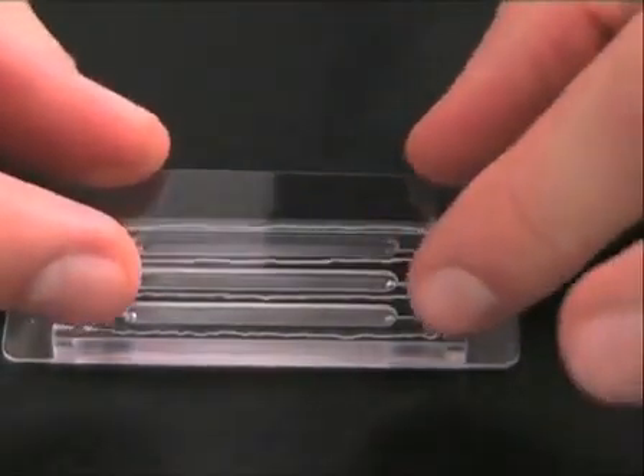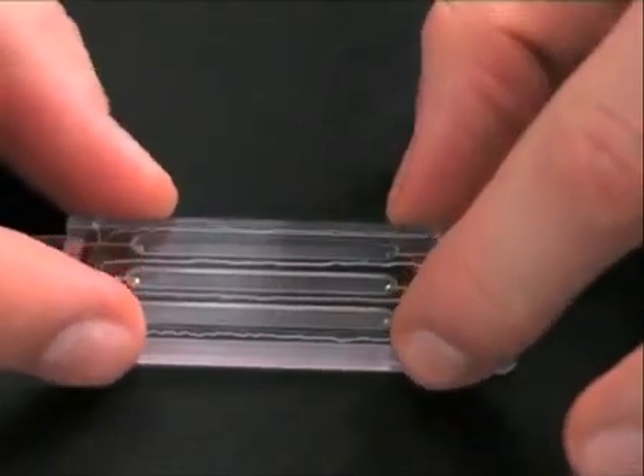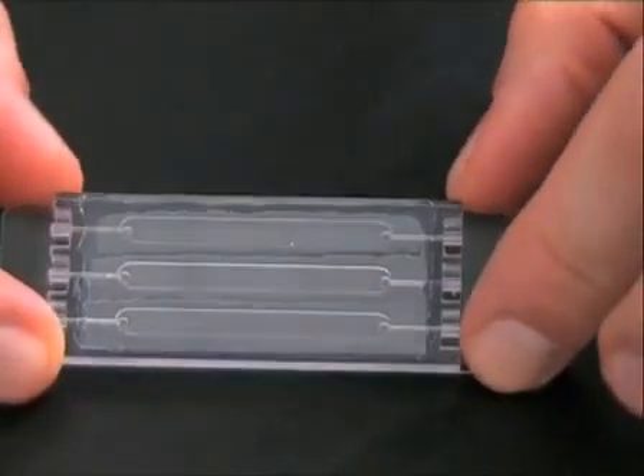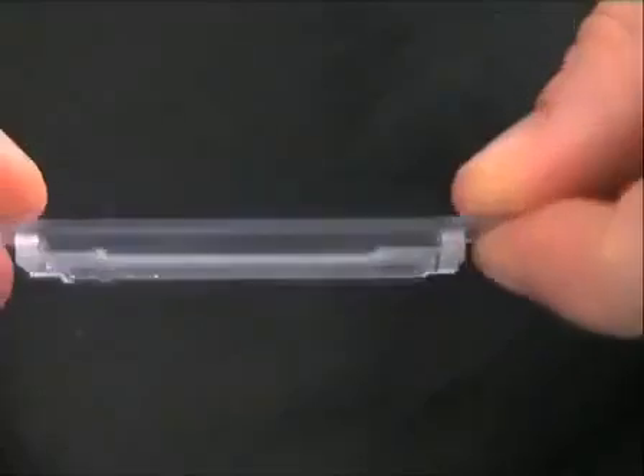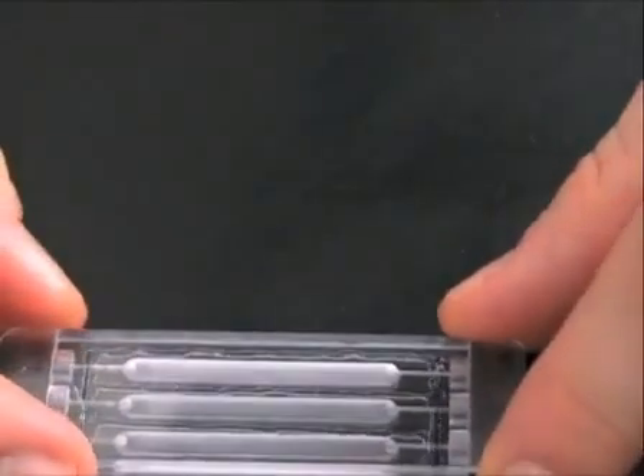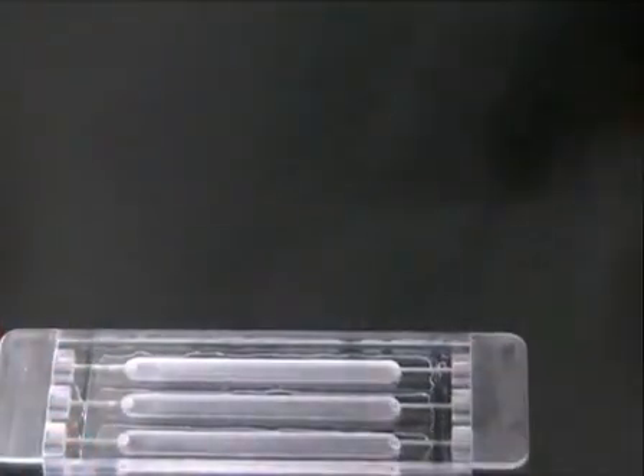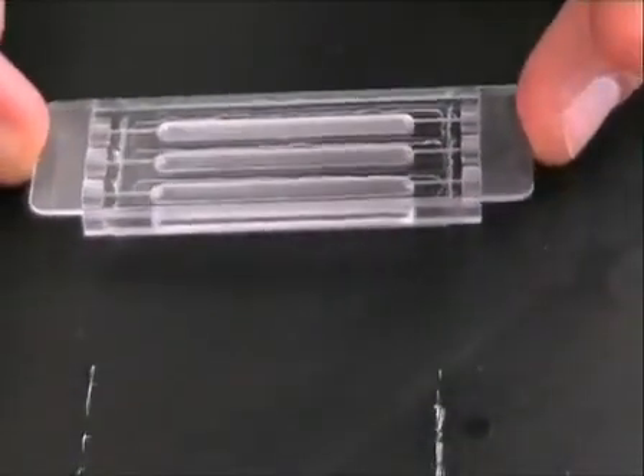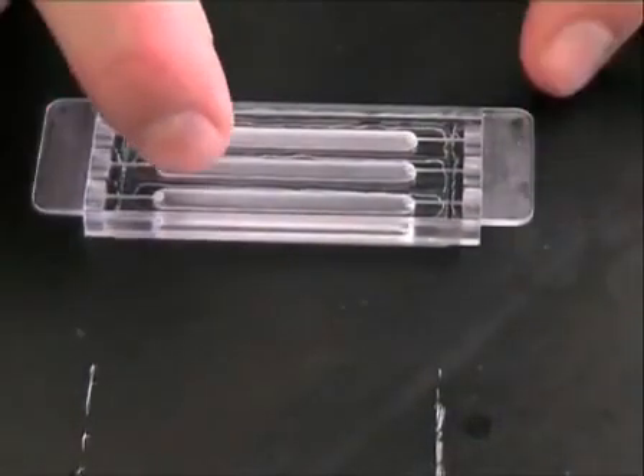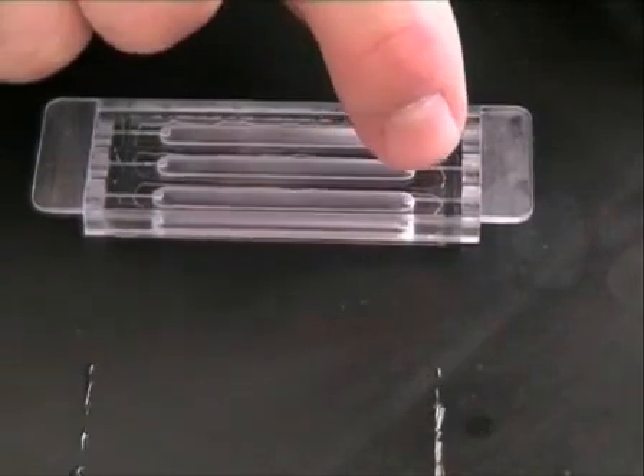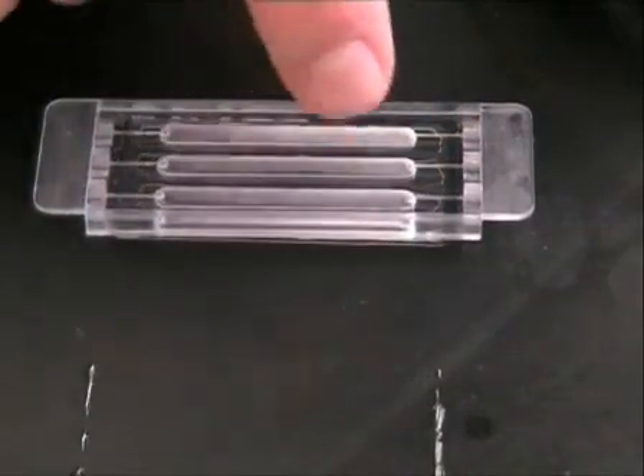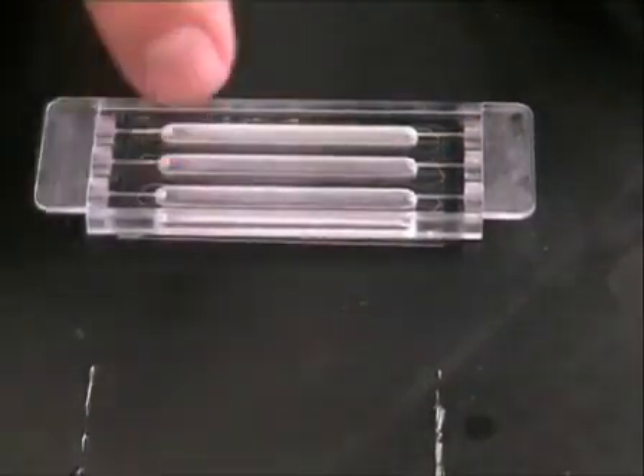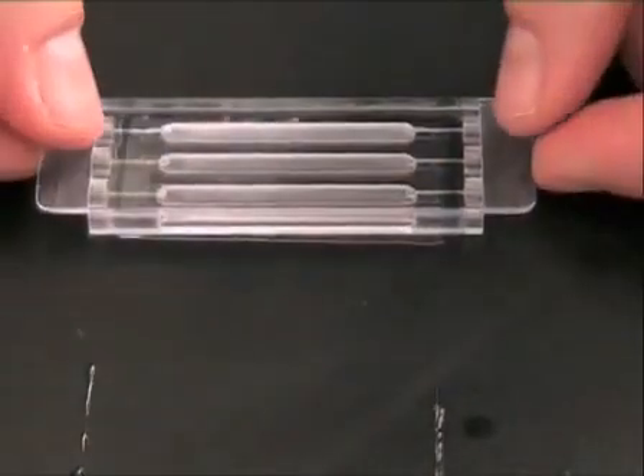Take a cover glass and gently place it on top of the silicone lines on the flow cell. As seen here, the cover glass will easily stick to the silicone glue. Turn the flow cell over and gently push down on the back of the flow cell with your fingers. This will ensure that the cover glass will attach in a flat manner according to the flat surface of the table.